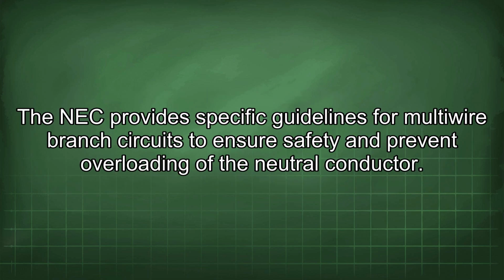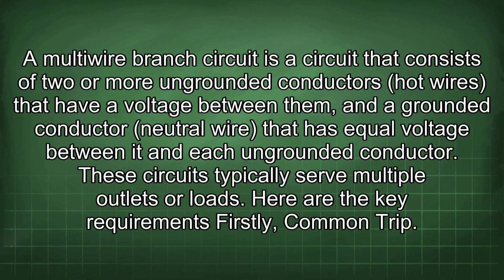The NEC provides specific guidelines for multiwire branch circuits to ensure safety and prevent overloading of the neutral conductor. A multiwire branch circuit is a circuit that consists of two or more ungrounded conductors, hot wires that have a voltage between them, and a grounded conductor, the neutral wire, that has equal voltage between it and each ungrounded conductor. These circuits typically serve multiple outlets or loads. Here are the key requirements.